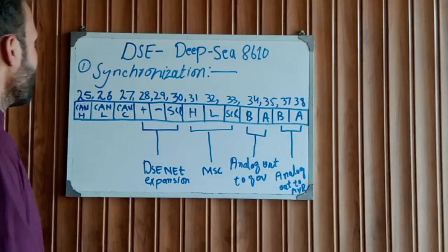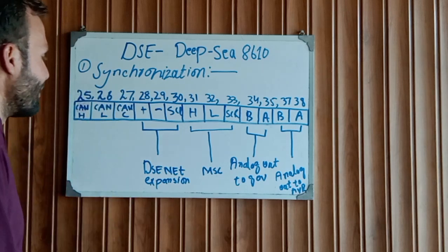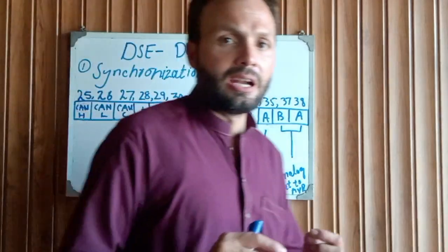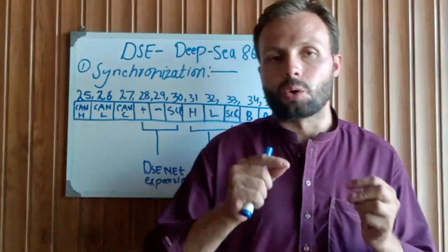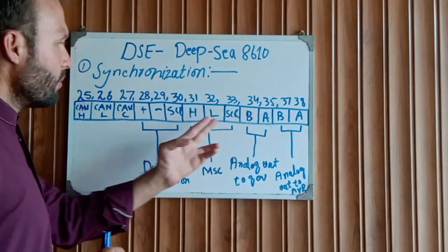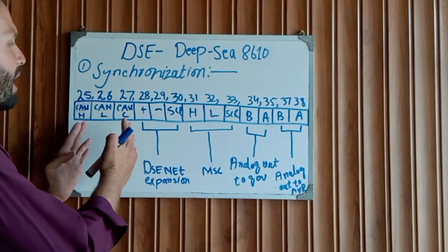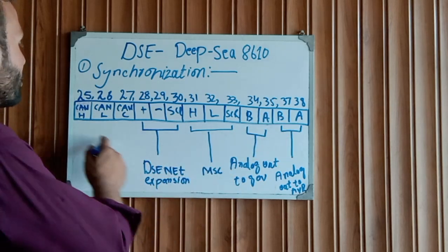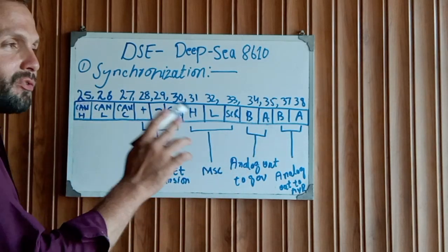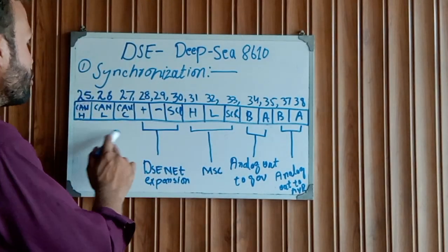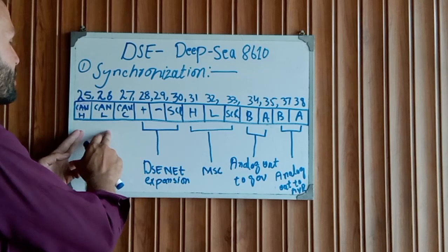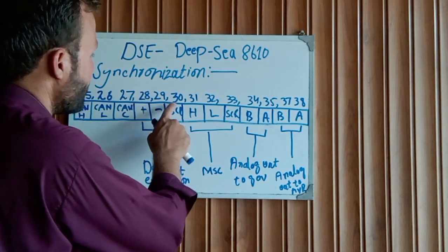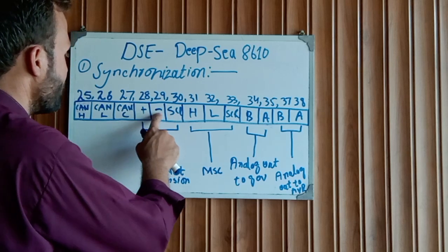As you can see, pin 25 and pin 26 and pin 27 - this is the CAN high, CAN low, and CAN common. CAN communication is used in electronic-type model generators which have engine control modules. All generators that are parallel and synchronized together, you need to put all generator wiring to each DSE from end to end with a 120-ohm resistor. This is a special type of wire used for CAN communication - shielded wire or screen wire. After that, pin 28 and pin 29 and pin 30 - this is the positive, negative, and screen wire.